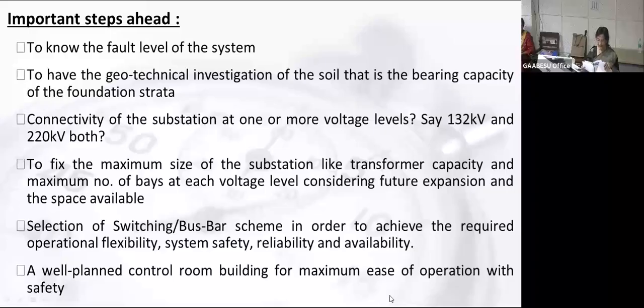Now, what are the technical steps? We have to know the fault level by doing a system study. Accordingly, we will choose the equipment ratings. For foundation requirement, the bearing capacity of the soil we have to look at. And connectivity, whether we should connect to the 220 kV grid or the 132 kV grid. All these factors we have to take into consideration.